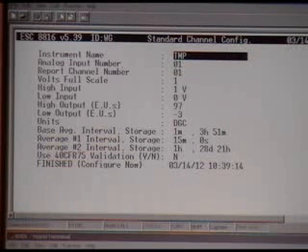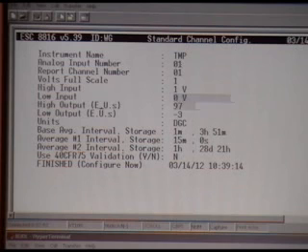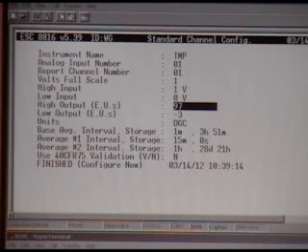And to change the temperature reading, we'll come down here to the high output and low output readings. I've already done this, but it was reading 98 and -2. And whatever numbers you put into the high and low, they have to equal a span of 100. So if you think of 97 plus 3 on the opposite side of 0, well, that's 100.